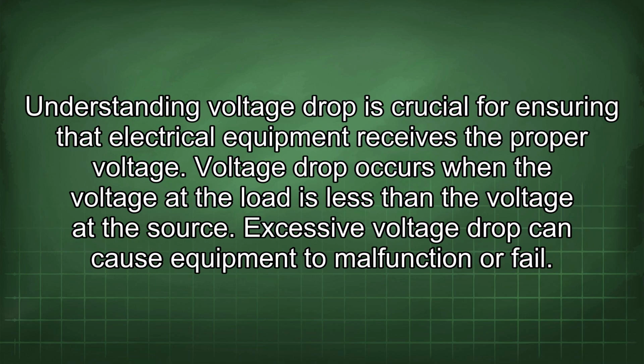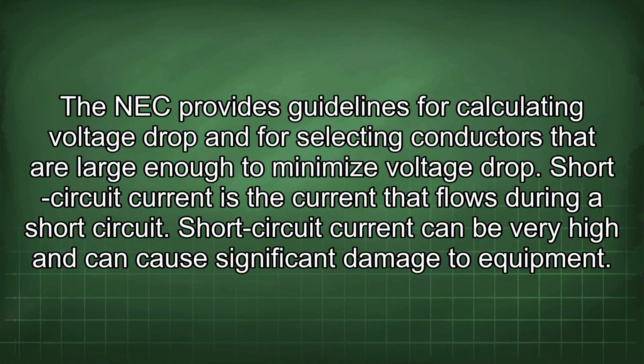Understanding voltage drop is crucial for ensuring that electrical equipment receives the proper voltage. Voltage drop occurs when the voltage at the load is less than the voltage at the source. Excessive voltage drop can cause equipment to malfunction or fail. The NEC provides guidelines for calculating voltage drop and for selecting conductors that are large enough to minimize voltage drop.